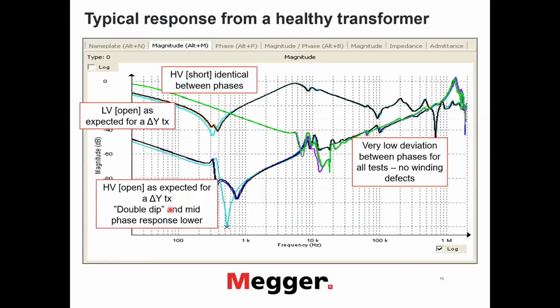So coming further to how the responses look. Here in this picture, I have a transformer which is in good shape. When we observe the curves, we have open circuit measurements of the high voltage side, so we have three phases here. I mentioned that phases should look similar, and they do, but for, let's say, star windings, there may be a single dip in one phase and double dips in two phases. This is perfectly normal, as well as for the short circuit measurement here.